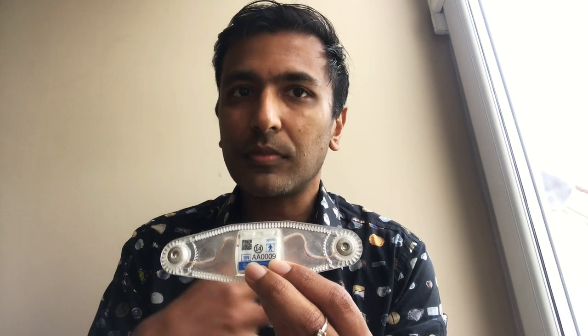The patch comes in a box that can be sent out to the patient — it arrives in their letterbox. It comes with written instructions and an instructional video, and the patient can apply the patch themselves. There are two electrodes here which are placed on the chest, and the patch attaches like that. It has a little button here as well. Once it's on, the battery activates and the patch starts recording every single heartbeat for the entire duration the patch is on the patient's chest. Patches are available in 24-hour, 48-hour, seven-day, and even 14-day versions.